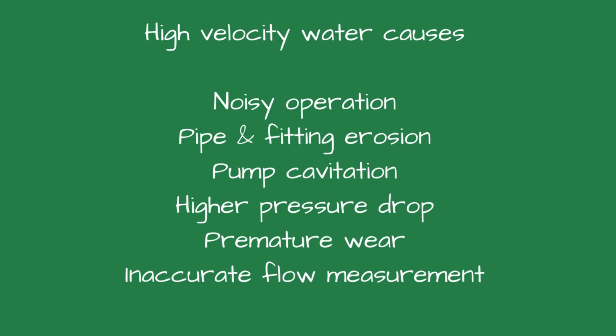In certain cases, high velocity can reduce pressure at the pump suction enough to cause cavitation, the formation and collapse of vapor bubbles that can destroy pump impellers and create loud banging or grinding noises. Higher flow equals more friction equals greater pressure loss across the system. This can make balancing difficult, lead to undersupplied zones, and force the pump to work harder, shortening its lifespan and increasing electrical costs.